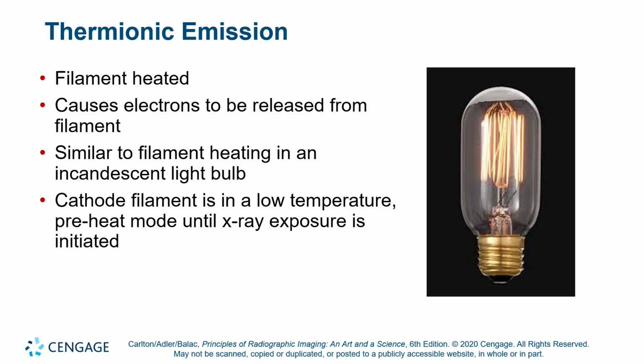So excitation is the electrons that are at a higher energy state, but they haven't passed the conduction threshold, so they can't leave. They have to relax back down. Okay? And so there's a sweet spot of how much current you push through to create excitation, but not necessarily ionization. Okay? The filament circuit is meant to get hot first before exposure begins.